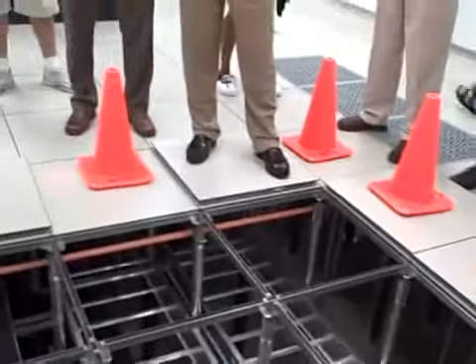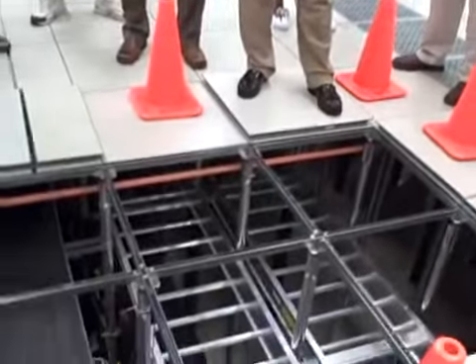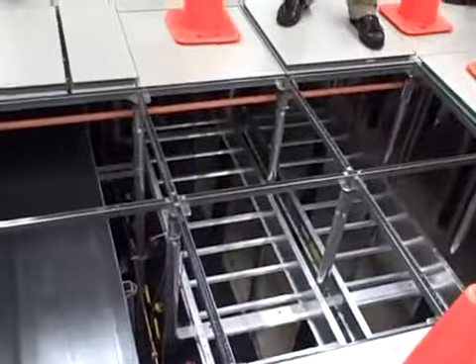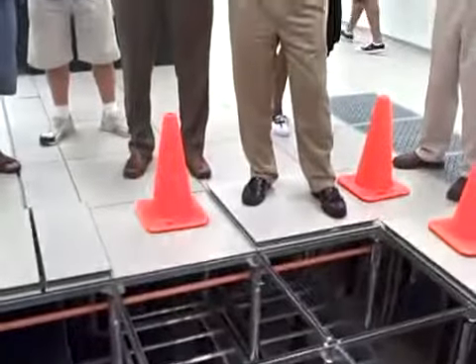So the rack that we're not going to look at weighs 7,300 pounds. I'm guessing my Honda Accord is like 2,500 pounds or something. We did some tests Tuesday and Wednesday, and you'll see some marks on the floor. And that's one of those things where you push harder and say, yeah, that's not even a mark. Each floor stanchion can handle 11,000 pounds. Each floor tile has a 2,500 pound rating.